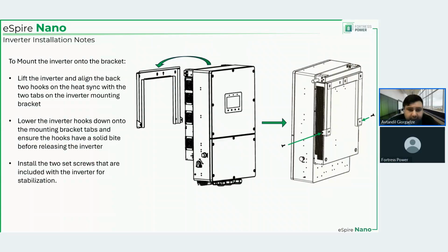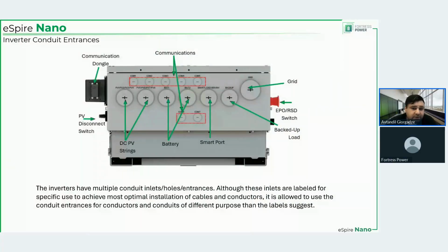Now, conduit entrances and stuff like that. Let's talk about those details, like what you have on the exterior of the inverter. Obviously, this is the view from the bottom. Communication dongle on the left side, PV disconnect switch. Nothing fancy. You can think of it as a switch that prevents the voltage from being applied to the MPPTs. You have conduit entrances for communication. You have conduit entrances for PV. You have a battery 1 and battery 2 conduit entrances. Additional communication here. Smart load or generator. This is for load port, and this is for grid.